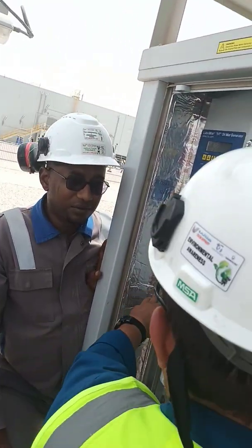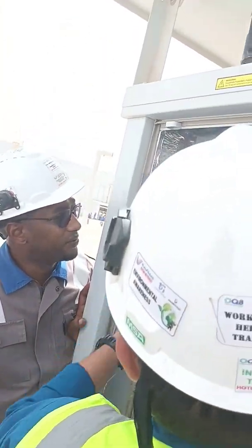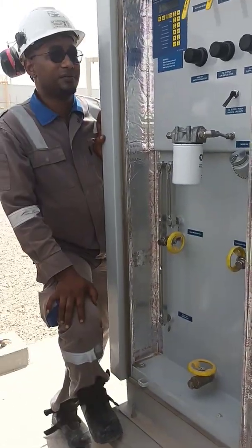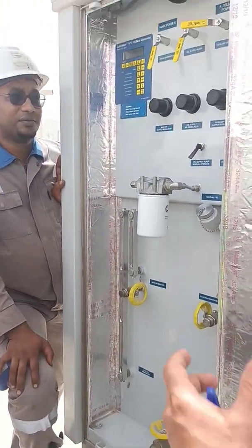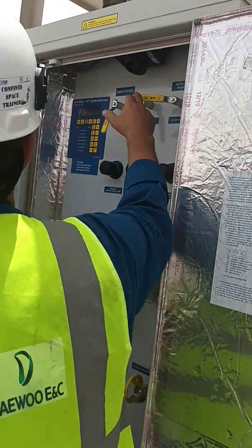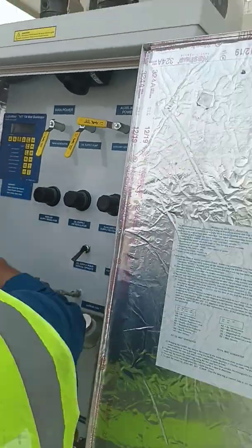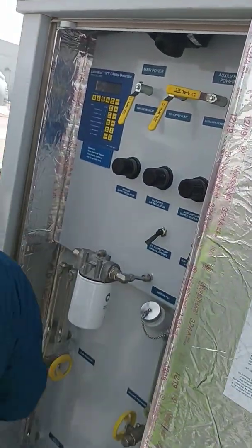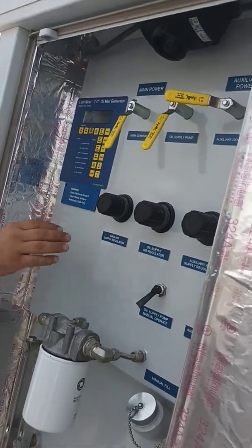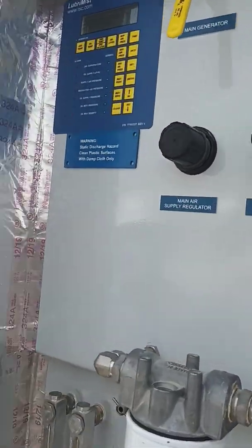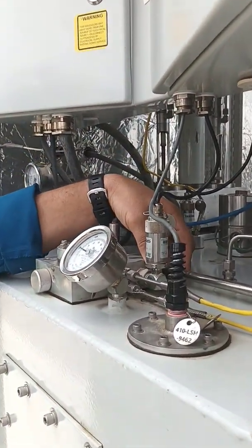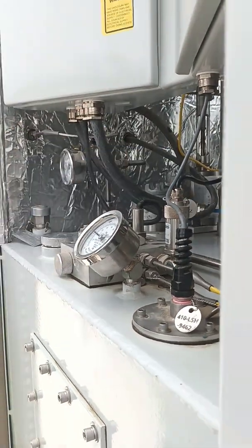My oil level here is the oil level in the main tank. Supply air is the air coming into my machine. There is a pressure transducer mounted on the manifold that is behind this. There is a manifold which is divided in three, 1, 2, 3. We have a sensor there for the supply air. Regulated air is the air coming from here. The reading for that is coming from this sensor here. That's my air pressure coming from the regulator. Okay?